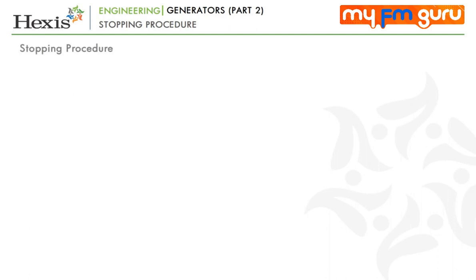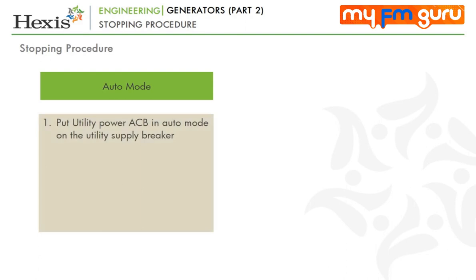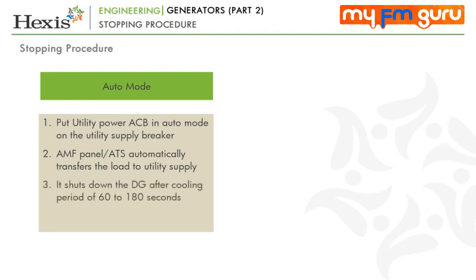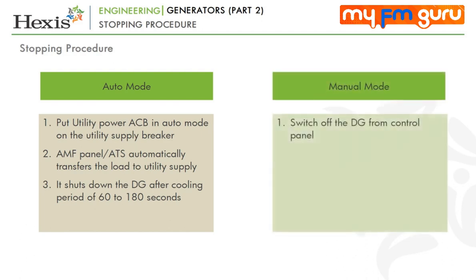Now that we know the starting procedure, let's look at the stopping procedure. Let's begin with the auto mode. In auto mode, put the utility power ACB in auto mode and switch on the utility supply breaker. The AMF panel or ATS will automatically transfer the load to utility supply and shut down the DG after the cooling period, which may last from 60 seconds to 180 seconds. In manual mode, switch off the DG from the control panel. After testing, ensure that control panel switch is turned to auto mode.